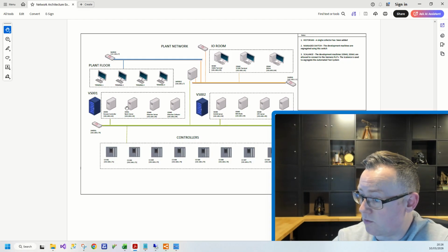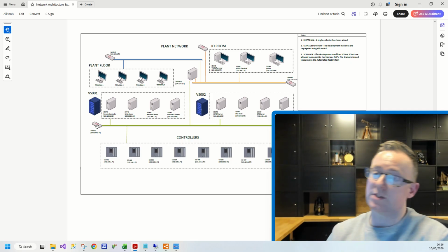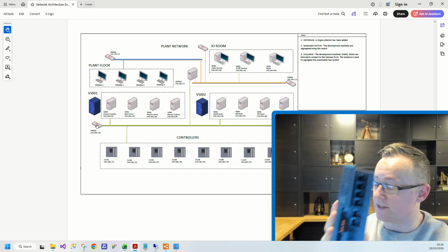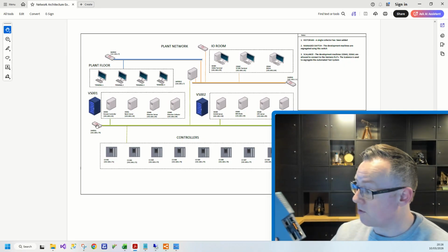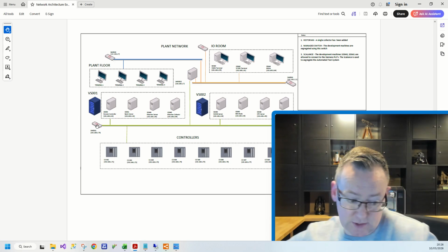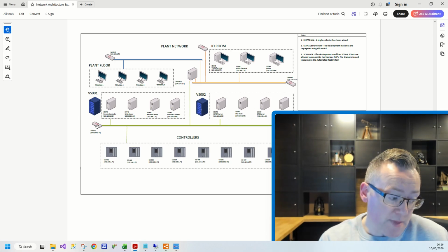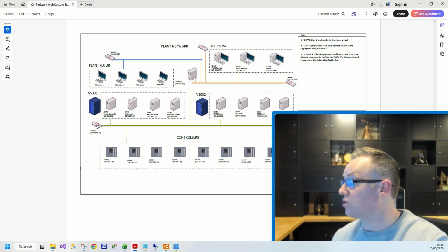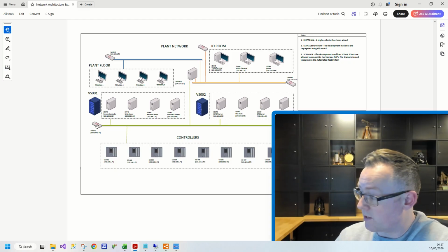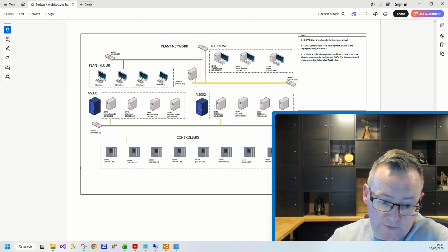It means that the switches in the middle have to be very, very well configured. So say, for example, I have here a firewall scalance switch, and the rules can do a lot of protection to devices. But the reality is that the Siemens devices, like this S7-1500, can do a lot of protection themselves. You shouldn't be depending on the firewall rules to do all this protection for you. It should really be at the device level, certainly for myself.